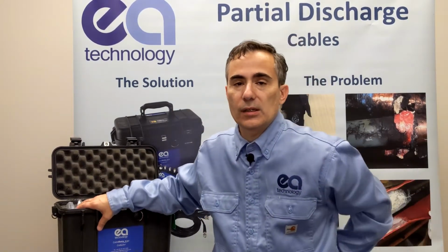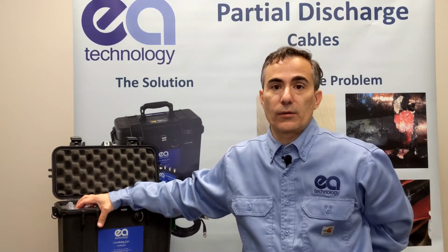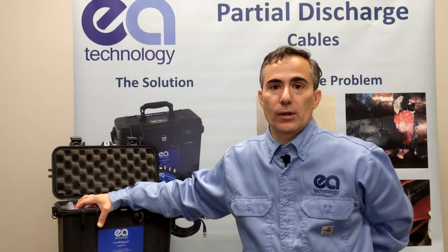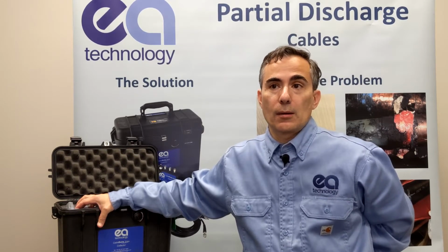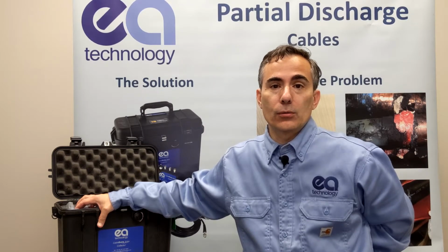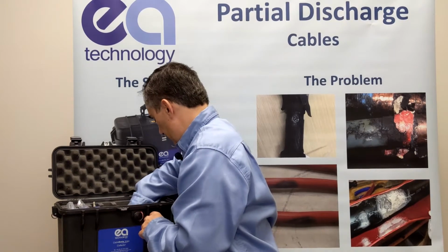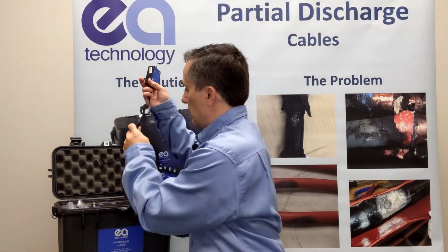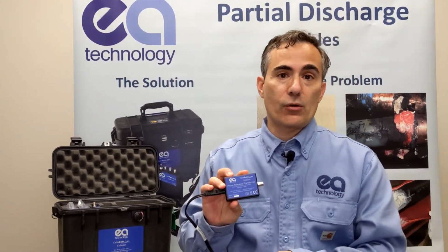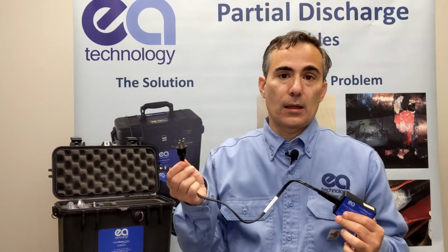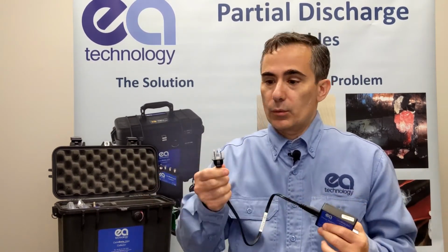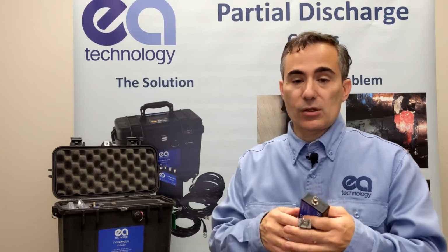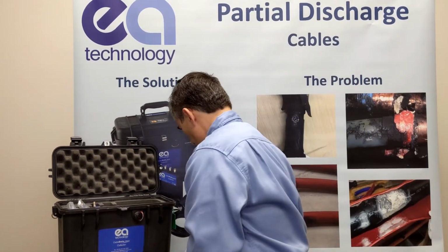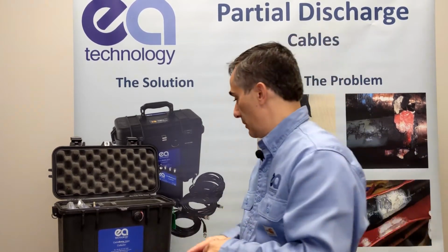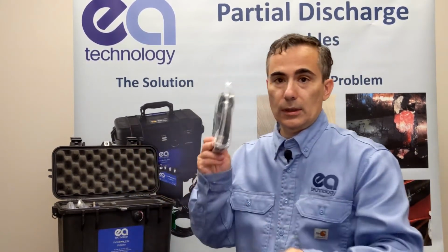The CTs are designed to pick up the phase frequency. For example, here in the US we have 60 Hertz frequency, but we need it accurate to the decimal. If for some reason it's not able to do that, included in the kit is this device, which is a phase reference transformer. It comes with a power cord with the appropriate plug for your country, and this will connect to that fourth location on the unit, with its own separate cable.